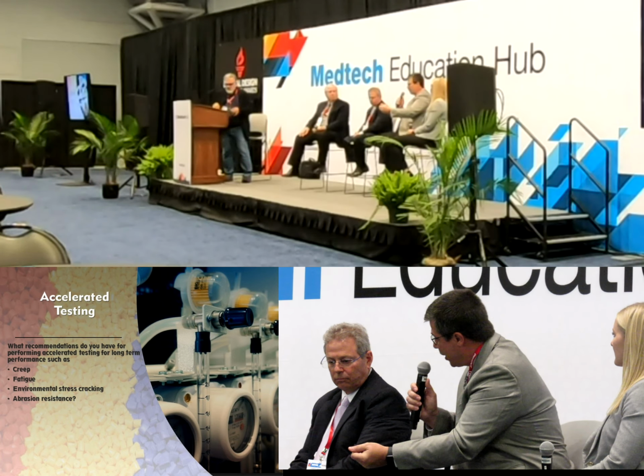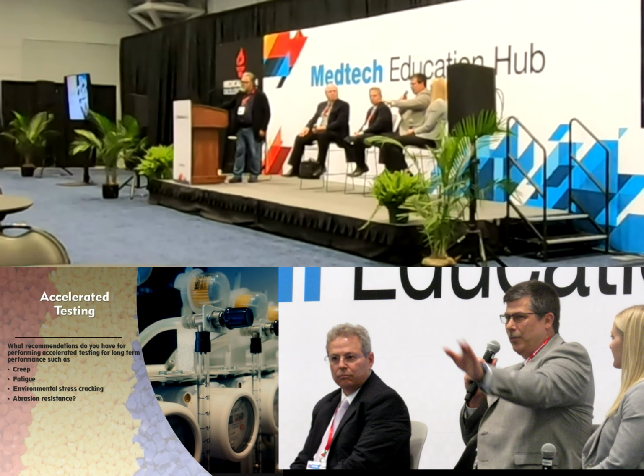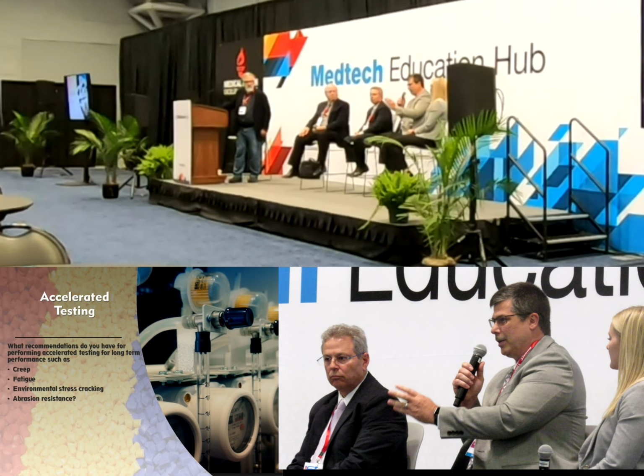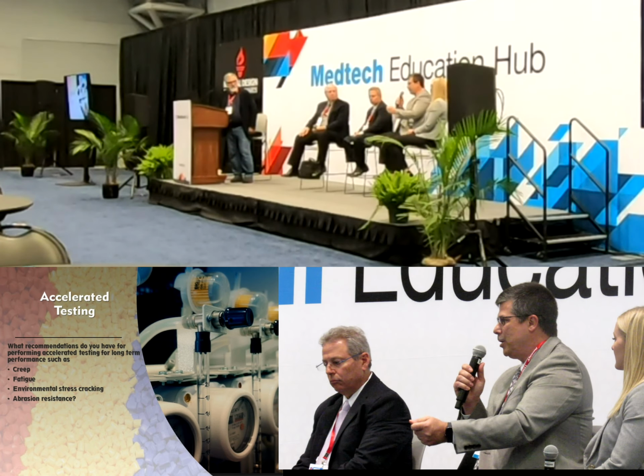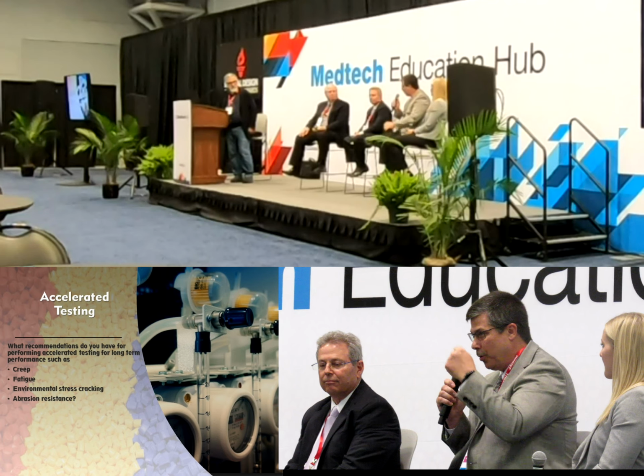to extrapolate. The issue is when you look at standard accelerated aging tests, everything was done based on a packaging, like a medical device package, and picked a value of Q10 Arrhenius equation based on Q10 factor of 2. Well, that's to kind of cover everything. But if you want to know the real value that's for each plastic, you need to go back to the company itself. You can definitely age plastics under that one standardized test, but in most cases, including whether it's polycarbonate or polyester, you're actually over-aging the plastic beyond what you think the life of the product's going to be.